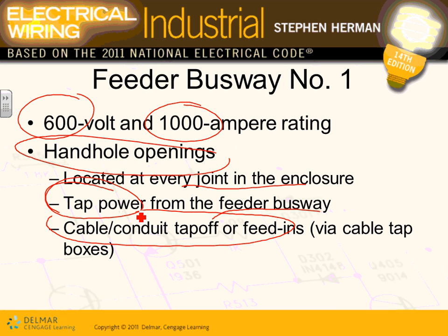So what they do, Adam, is they take right in here. I don't know if you guys can see right in here. They have a place where they tap power. This is not a plug-in. This is a box where you bring a conduit to it and you tap into that feeder. Any comments, guys? Any questions about feeder number one? Feeder number one is in our plant. It's going right along the perimeter of the manufacturing floor, and it feeds multiple panels. Believe it or not, they're feeding panels out of that feeder number one.